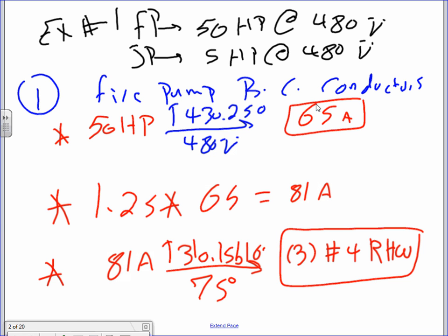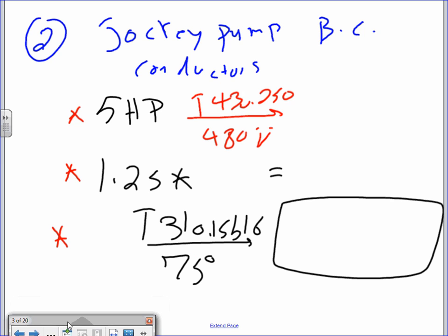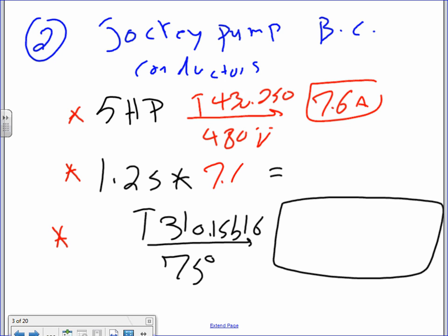Okay, shall we go to the jockey pump? This is number 1. And we're following a sheet like this. You see that sheet in front of you, right? Okay, good? All right, so let's go to the second one. Second one, jockey pump, 5 horsepower motor. We're going to go to the 5 horsepower motor, 430.250. You're going to have 7.6 amps. And then the same thing, 7.6 amps multiplied by 1.25 gets you a beautiful 10 amps.